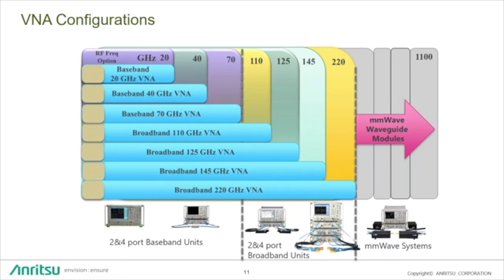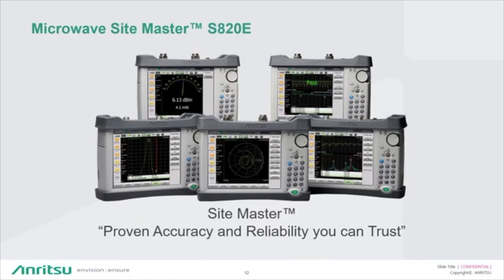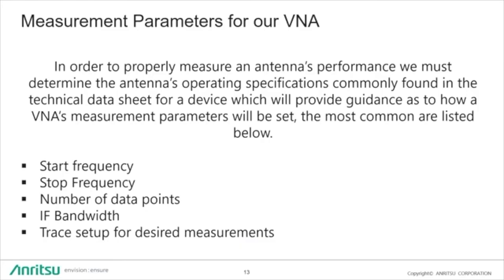When measuring antennas, we have to measure across the entire spectrum. We can do that with different models of Anritsu vector network analyzers — benchtop models going up to terahertz range, and handhelds, which are very common in cellular base station maintenance for measuring cables and antennas. The first step is to determine the specifications from the technical data sheet, which tells us the start and stop frequencies. We then choose the number of data points and IF bandwidth, and set up traces for our desired measurements.